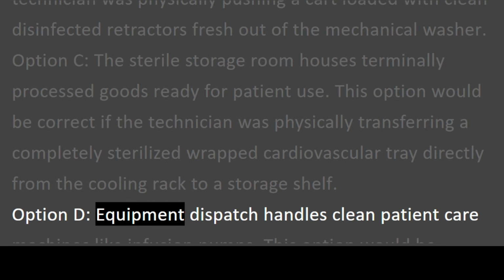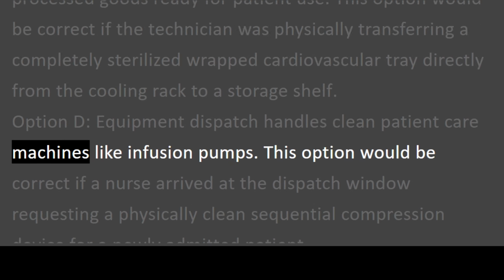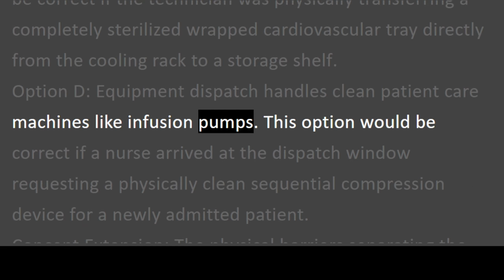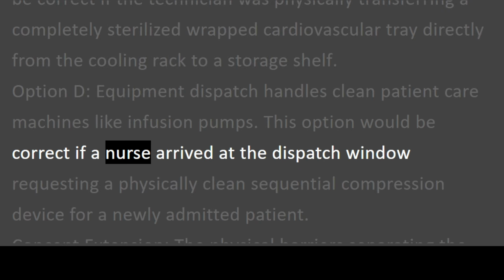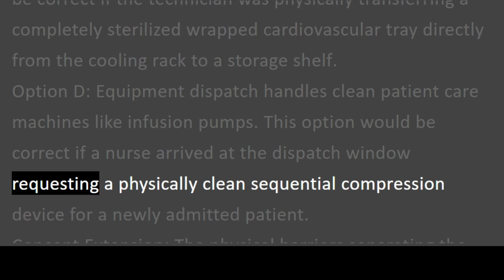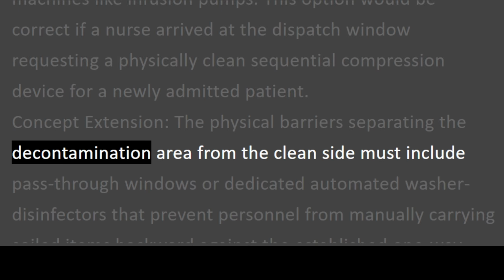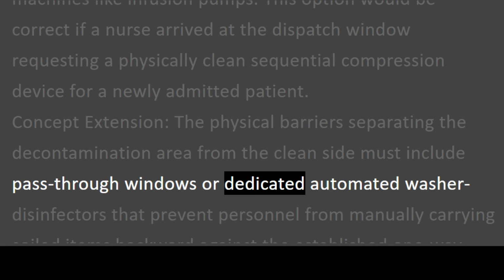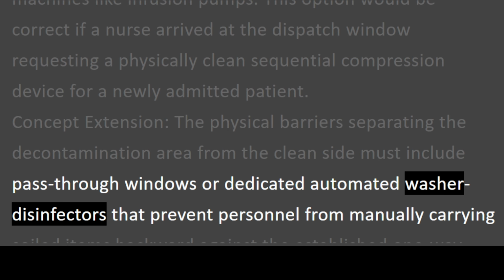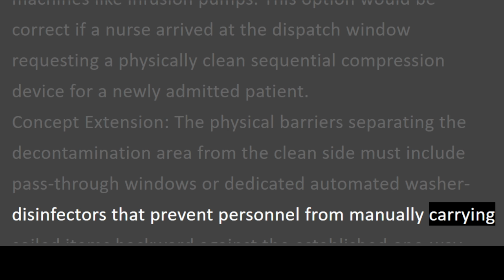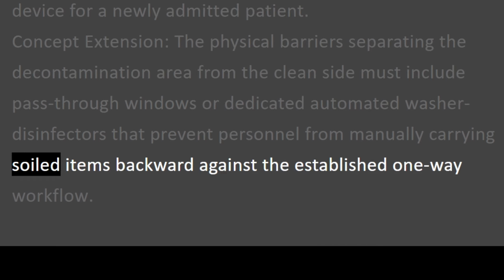Option D. Equipment dispatch handles clean patient care machines like infusion pumps. This option would be correct if a nurse arrived at the dispatch window requesting a physically clean sequential compression device for a newly admitted patient. Concept extension. The physical barriers separating the decontamination area from the clean side must include pass-through windows or dedicated automated washer disinfectors that prevent personnel from manually carrying soiled items backward against the established one-way workflow.